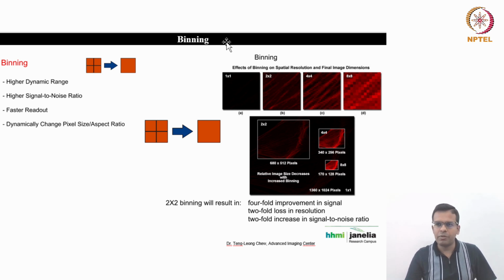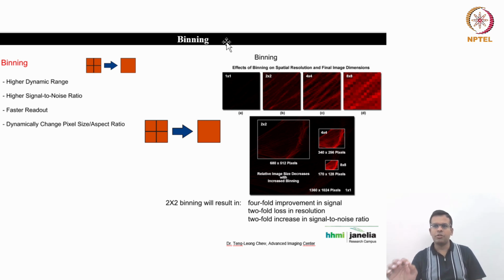Whatever microscope software you are using, it always gives you an option of binning. So what does this binning option do? It combines the electrons from 4 pixels, and all these electrons go to the readout register as 1 pixel. This is how it can speed up the processing.